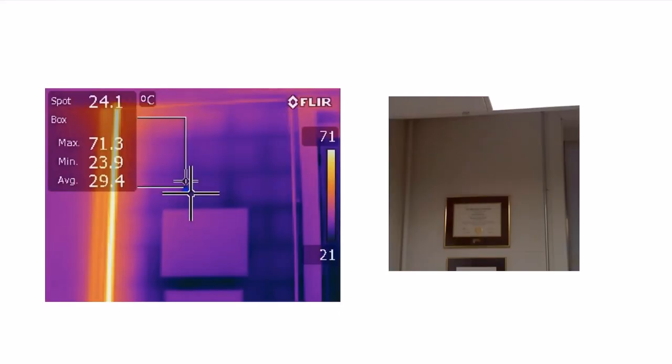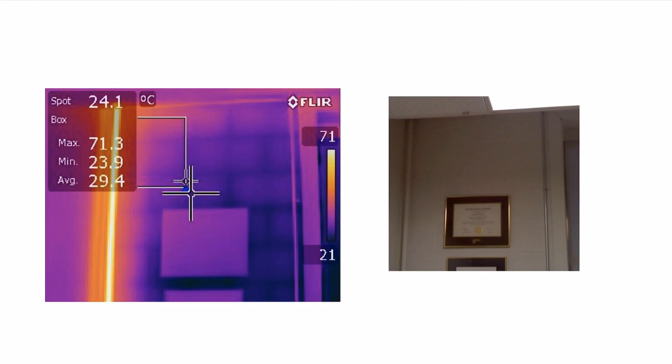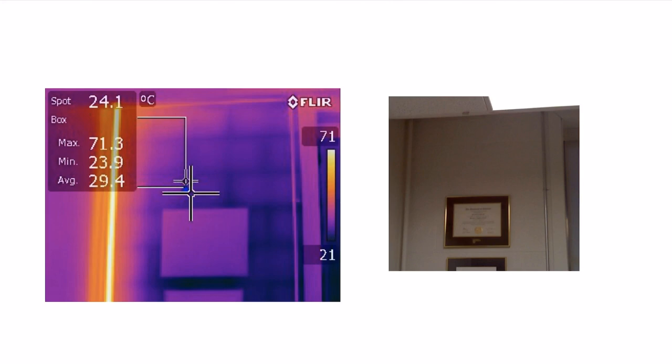Here's a picture of my office wall. We have some interesting features. In the visual image, here's a picture frame with a metallic frame and glass surface. Behind it is the cinder block wall. We have some electrical conduit and some pipe painted with the same paint as this wall. This paint is going to have a constant emissivity. Interestingly, when I look at this wall surface, I can see the individual cinder blocks and the grout between those cinder blocks. Because this is all of constant emissivity, I have a good idea that the relative temperature between them is an accurate representation. I can identify all the grout lines which are reading with a darker color, which means lower temperature. The grout lines on this exterior wall have a higher conductivity than the cinder blocks which have a large air gap in them. I'm having more heat transfer through all of these grout lines, and maybe this wall should have been better insulated when it was built.